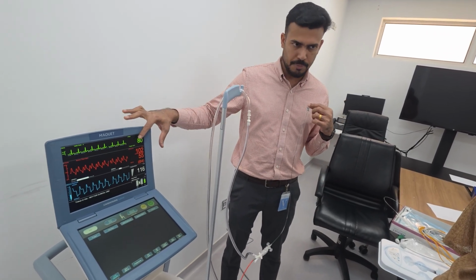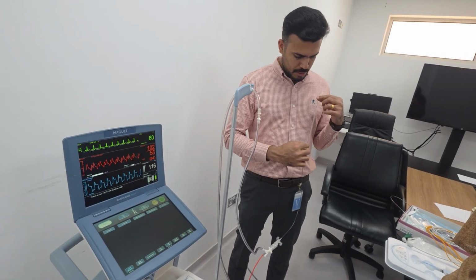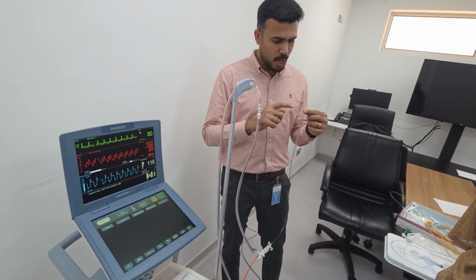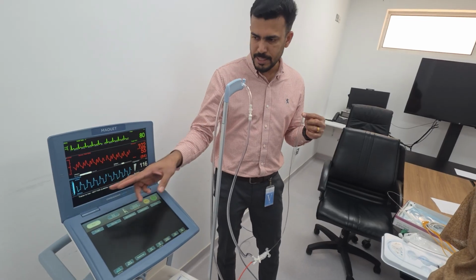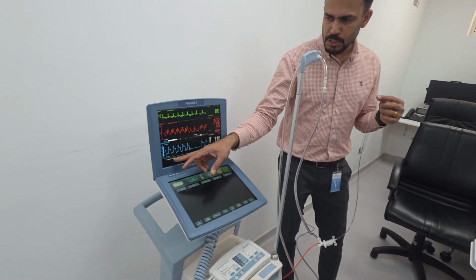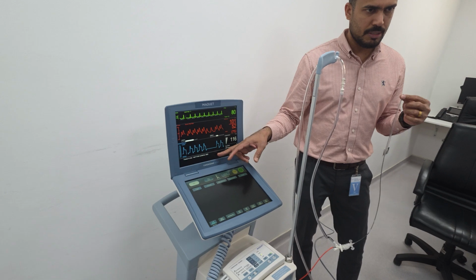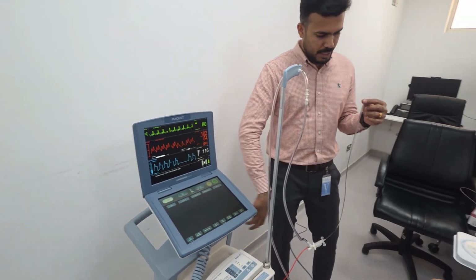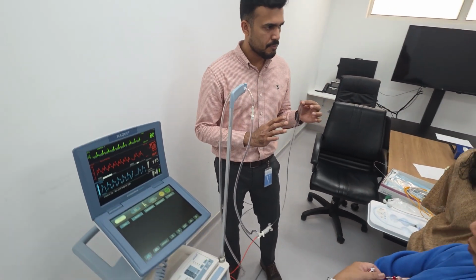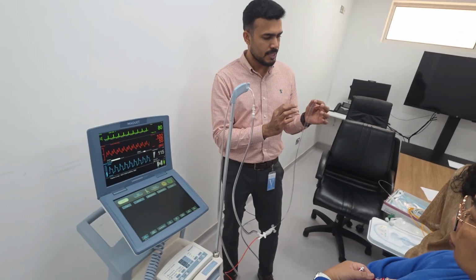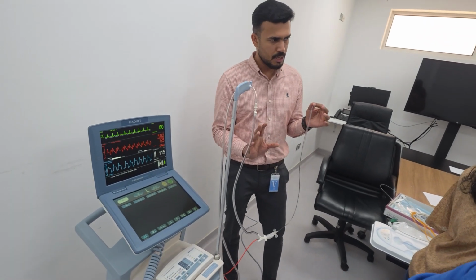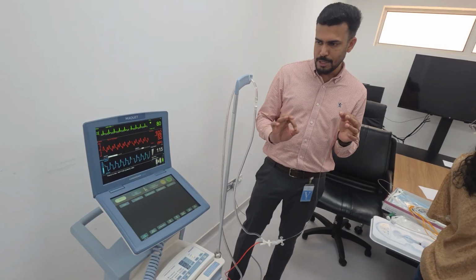See, it changes to ECG automatically. So every 2 hours the machine will initiate an autofill along with the fiber calibration. In between, you can see the machine is doing the autofill procedure and fiber optic calibration. Every 2 hours it will remove the helium and refill with new helium, to make sure it has 100% helium and no water condensation. That process will happen every 2 hours.